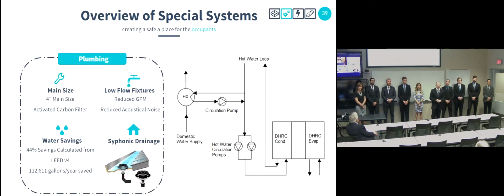To maintain a high quality of water in the building for our athletes, the water will be run through an activated carbon filtration system that will remove unwanted particulates from the water. The hot water for the building will be heated from a loop from the hydronic hot water supply. This will be done using a hot water tank with an integral double-walled heat exchanger. This double-walled heat exchanger prevents cross-contamination between the domestic hot water and the hydronic hot water systems. And also, for the low roof areas and possibly for the large roof areas, we're looking at using a siphonic drainage system. This system allows us to use smaller pipe sizes for rainwater drainage and also decreases installation time and installation costs.